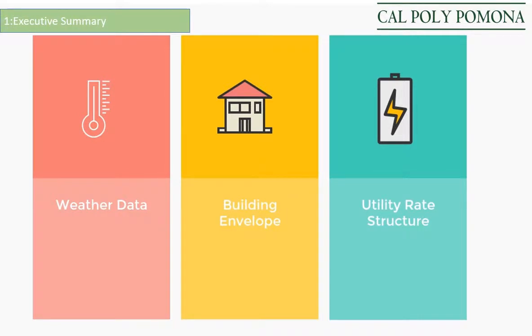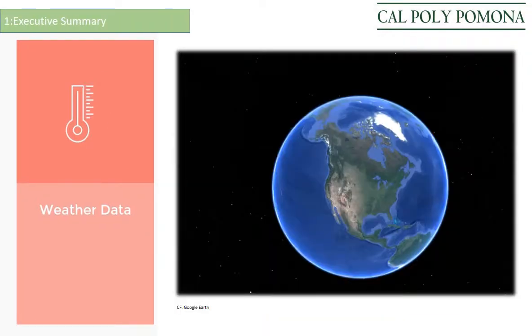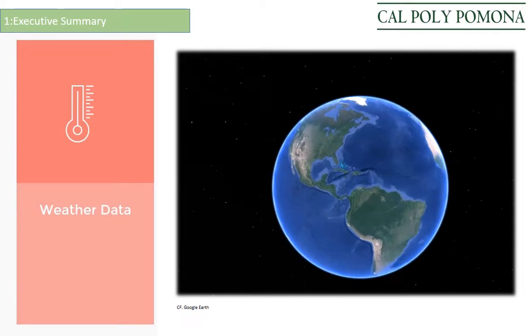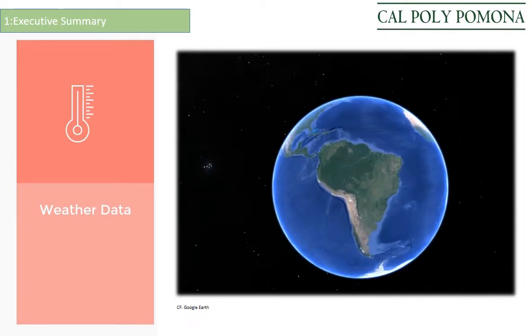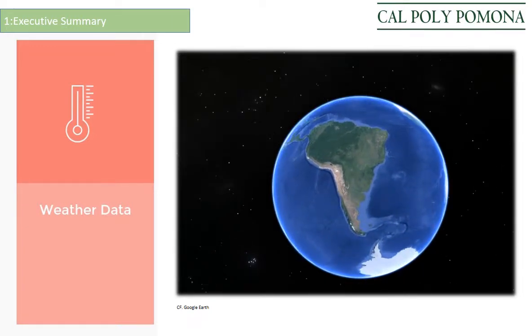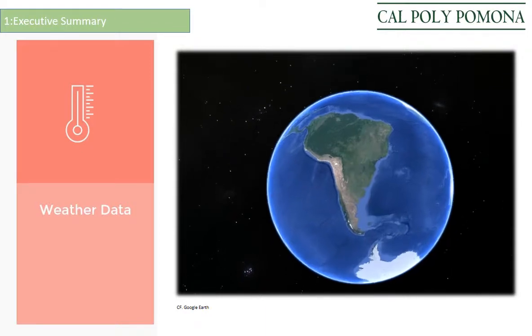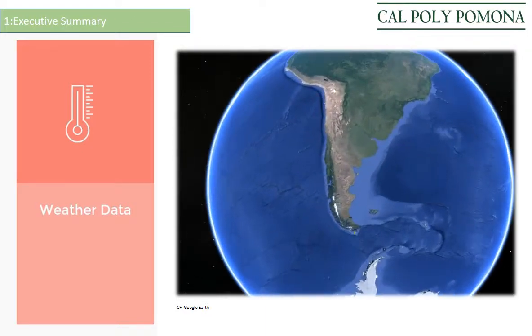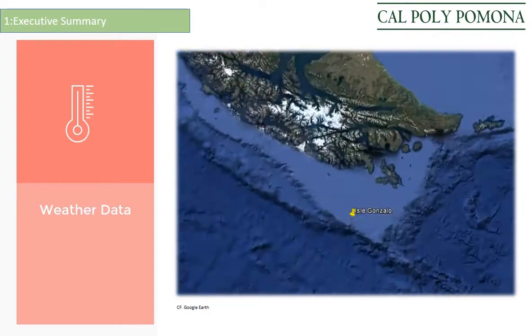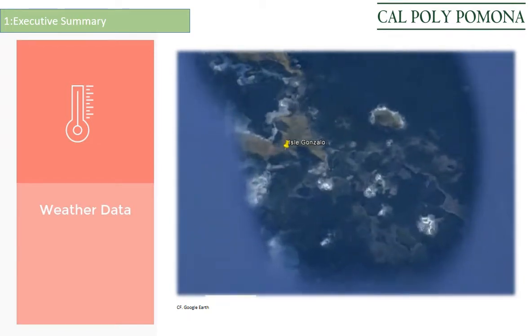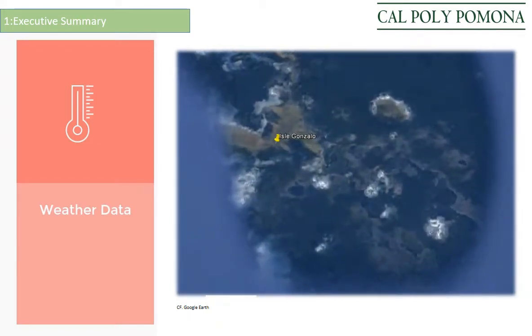Design parameters. The Diego Ramirez Island is located south of Chile, close to the South Pole. The average temperature is 40.9 degrees Fahrenheit. The island has a relative humidity between 70 to 90% average year-round, which is relatively high. Yearly rainfall is 43 inches per year. Wind speeds are usually above 10 miles an hour year-round. This is a key factor in infiltration. The island has good outdoor air quality because it is very remote.